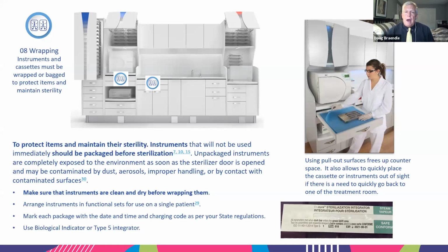Two different types of BIs. A BI you can run internally with an incubator in your own office, or you can send them out to be done with an outside service, and they just report back to you. So the issue with that, even if we have a BI that you're running in your own office, the incubators, 3M's got some fast ones now, but incubators for the most part are going to be anywhere from 10 hours to 24 hours. So here's my issue.